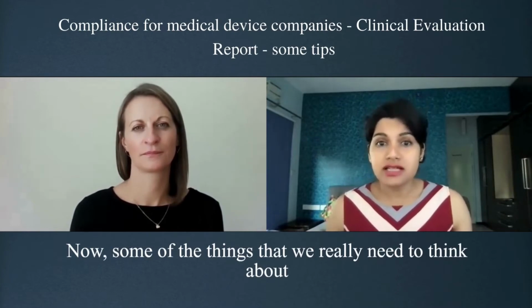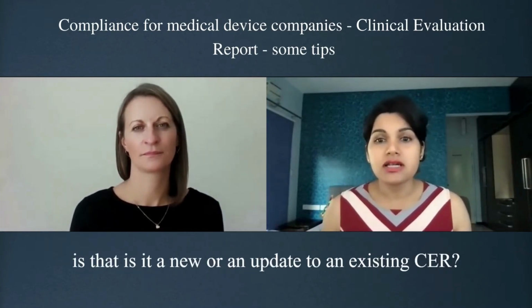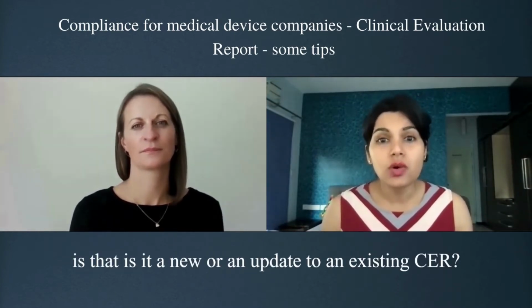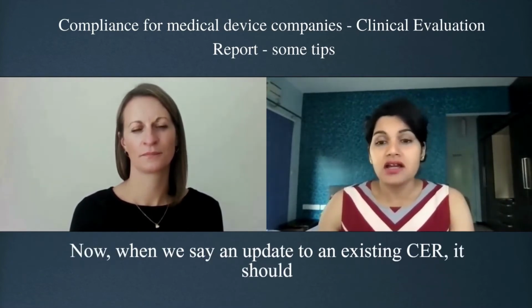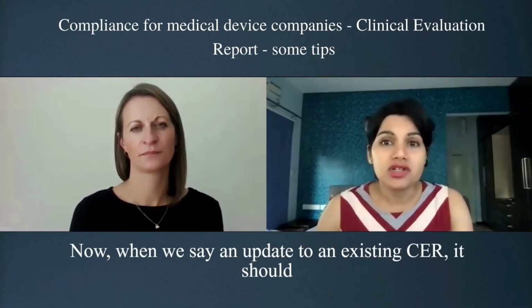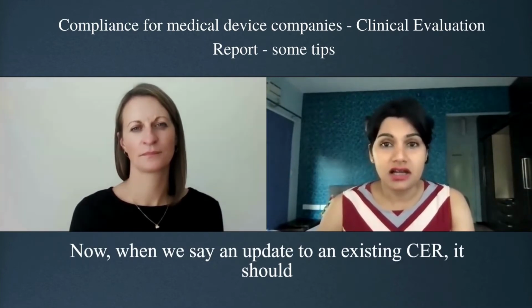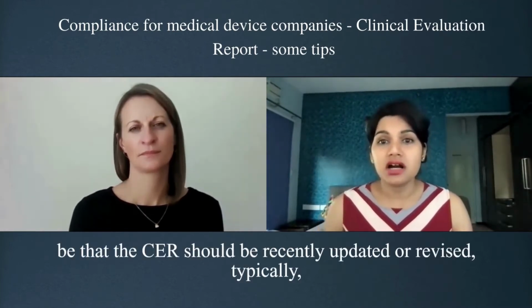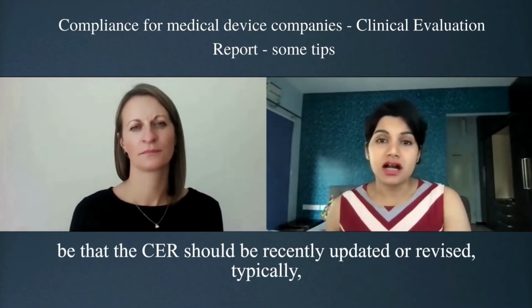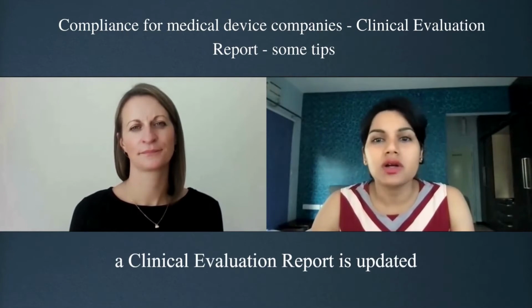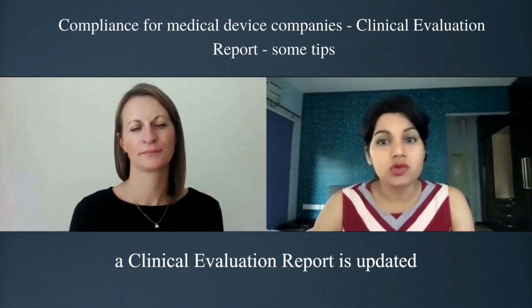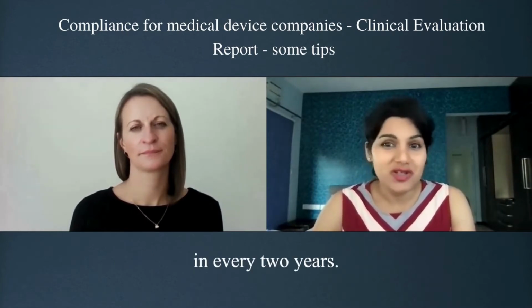Now, some of the things that we really need to think about is, is it a new CER or an update to an existing CER? When we say an update to an existing CER, it should be that the CER has been recently updated or revised. Typically, as per the regulations, it's required that a clinical evaluation report is updated every 2 years.